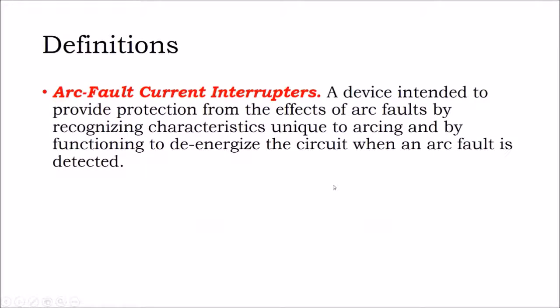Then we have an arc fault current interrupter, which is a device intended to provide protection from the effects of arc faults by recognizing, yada yada. Arc faults are different than ground faults. Ground faults are when the electricity goes from that ungrounded conductor, that high voltage conductor, and it touches a low voltage component, like a metal part that has no voltage on it, and it's connected to the equipment ground conductor, and the power spills over into the EGC and flips the breaker on your panel.